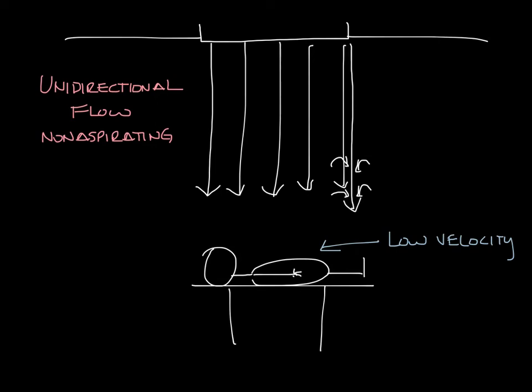So let's talk about the air velocity. The air coming out of your unidirectional diffuser is most likely colder than room air. We'll call it 55 degrees up here. And this cold, slow moving air is going to want to fall to the floor.